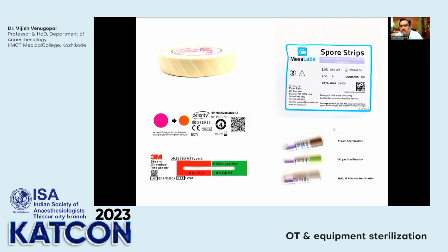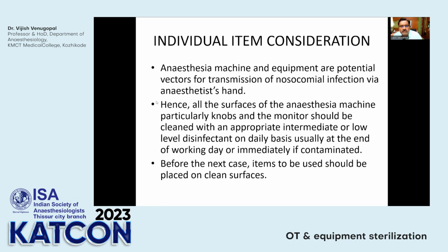The other one is using the spores, which can be either spore strips or spore vials, where specific bacteria are used for testing the efficacy of specific sterilization methods. For example, for steam, people use Bacillus stearothermophilus. So that just takes a longer time because it has to be incubated to know whether the organism is growing. Now you have fast incubation, you can get results within almost an hour, whereas previously it used to take 2 days.